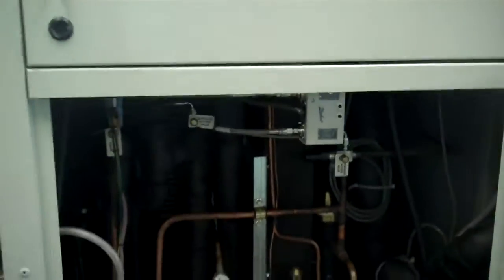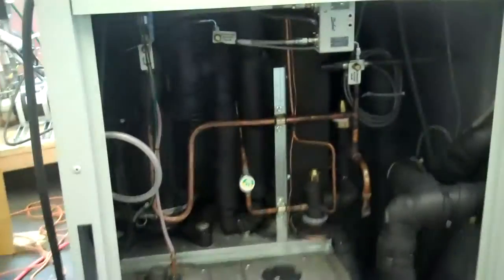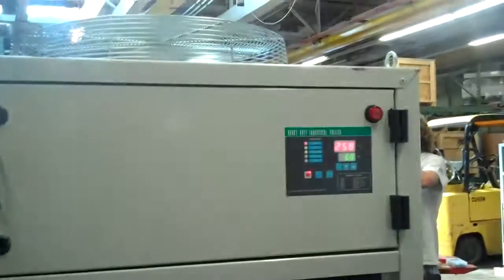It's important when you run the chiller that you keep the side covers on. You can hear the chiller just started. And these side covers on the inside have insulation that's at an angle. It's important that you have them installed correctly so they come up flush and make a seal against the condenser. Because otherwise there won't be the proper airflow to chill properly. It will actually go into alarm, high pressure alarm, if that's the case.